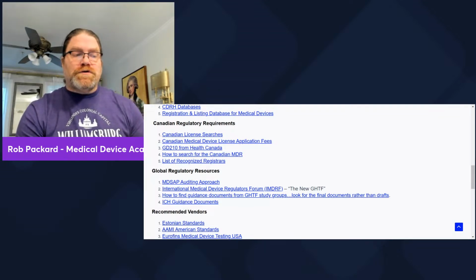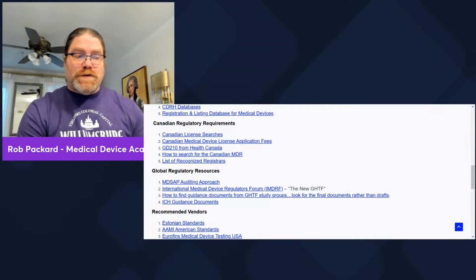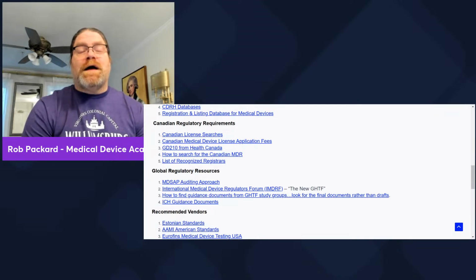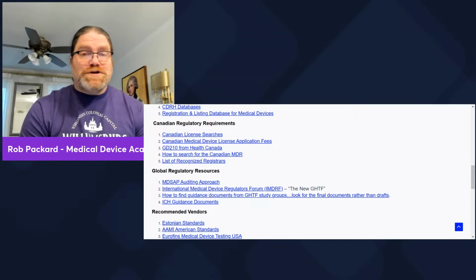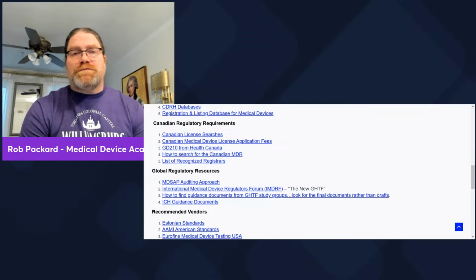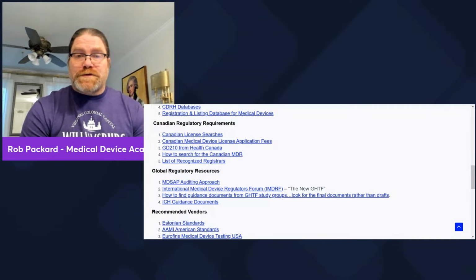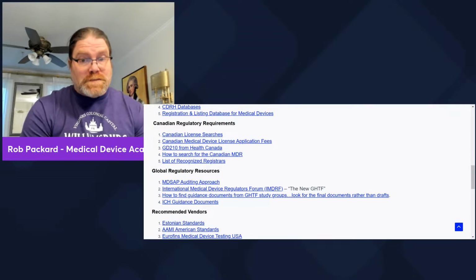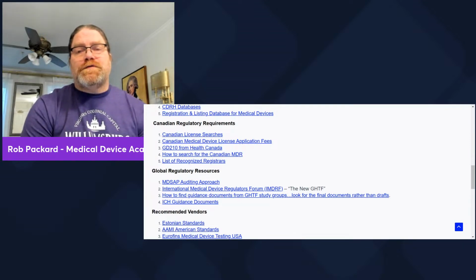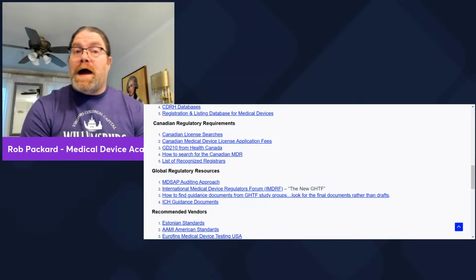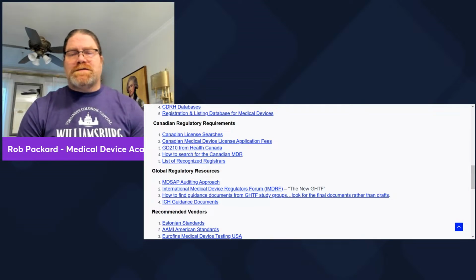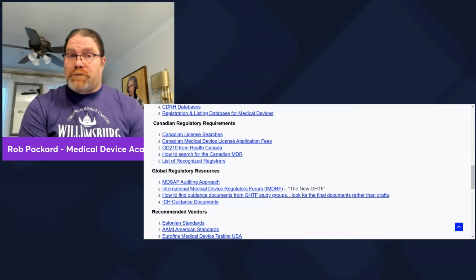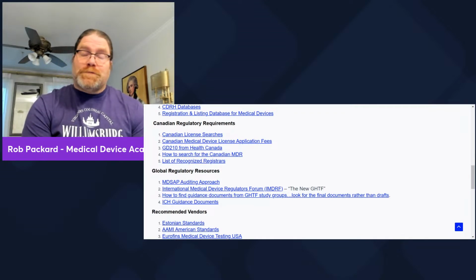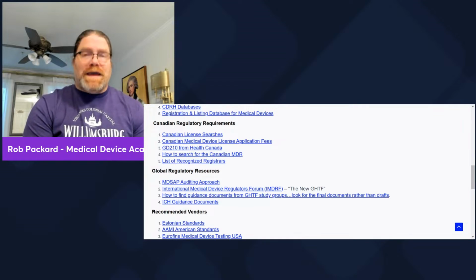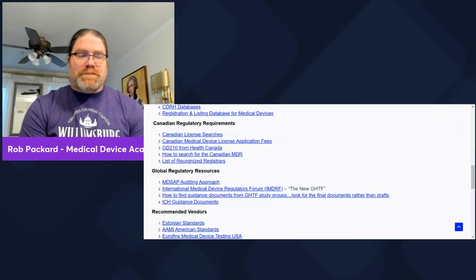So we learned what resources you go get on the Canadian website. So you would keep links on that website there. One of the most common ones was, how much does it cost? How long does it take? Well, that information could be found on the Canadian website. They have guidance documents there. So they have excellent guidance documents for recalls, post-market surveillance. If you need help writing those procedures, go look at those guidance documents and plagiarize. Use a lot of content from those guidance documents that Health Canada has on how to do a recall, how to do a mock recall, how to do post-market surveillance activities, how to write a post-market surveillance update report, a PSUR, that's required for Europe. Europe doesn't provide the best guidance document on how to do that. Canada does. So Canada has some really great guidance documents that you should look at.